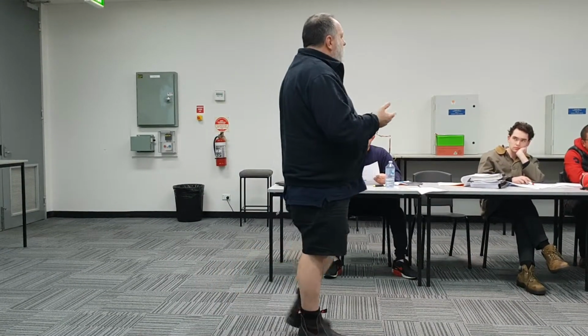Now when you get down to the H section, from H down to communal loads, if I had, for example, 18 light fittings, and there were 150 watts each, I would divide that 18 light fittings by 3 across the 3 phases, because we've got to spread the load across the 3 phases. So 6 into 18 goes 3 times. So 6 per phase, 6 times 100 would be 600 divided by 230, and that would give me my current. Is that making sense?